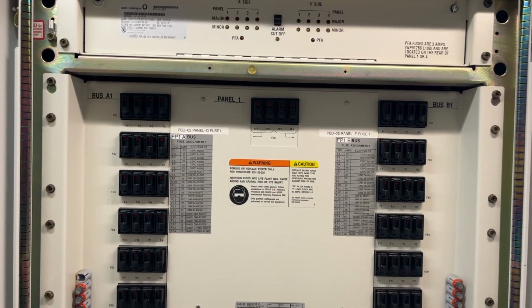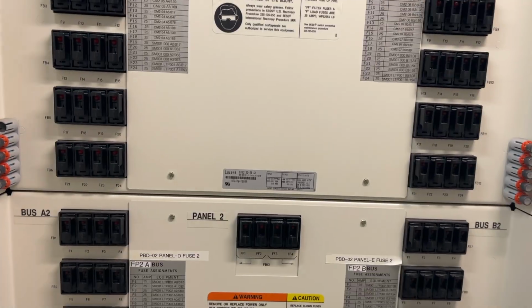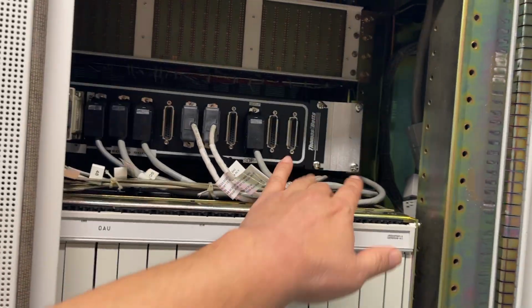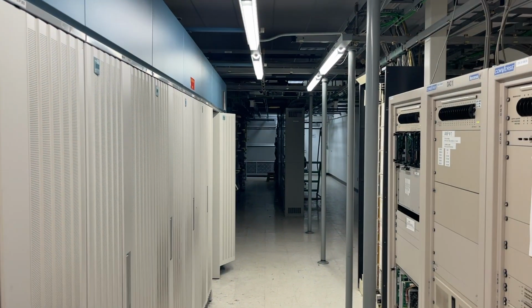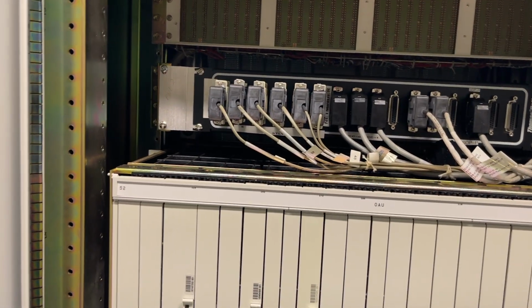Here's the power distribution frame, just a bunch of DC circuit breakers with the spares ready to go, and that's what controls the power for all this stuff. Then we have the maintenance module. This one I've been troubleshooting. I had to run another serial cord to the equipment on that end to interface with the T1 card, because they weren't able to remote into this building.